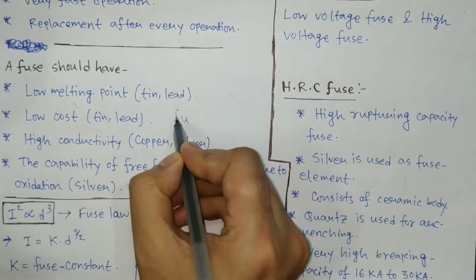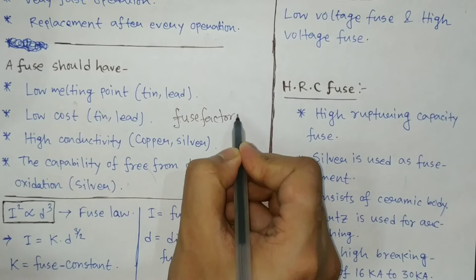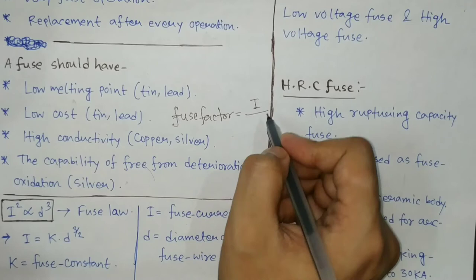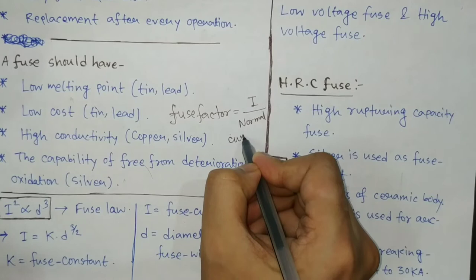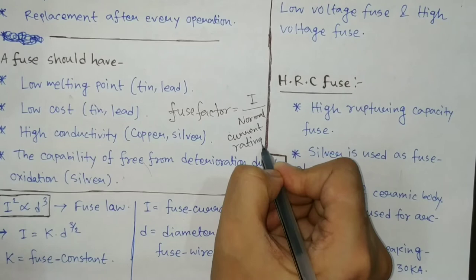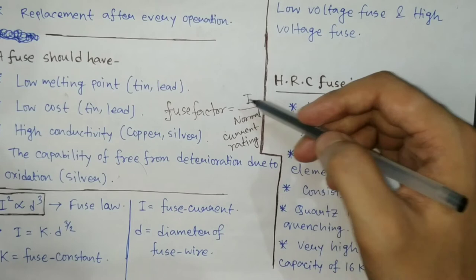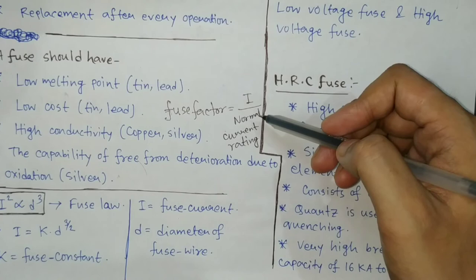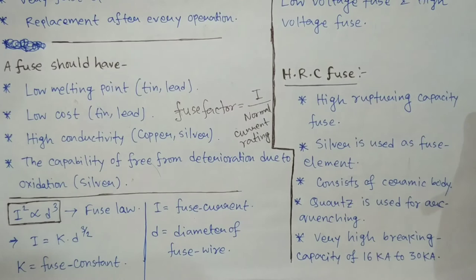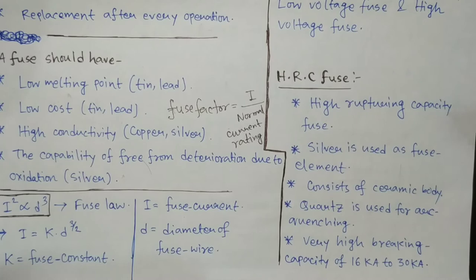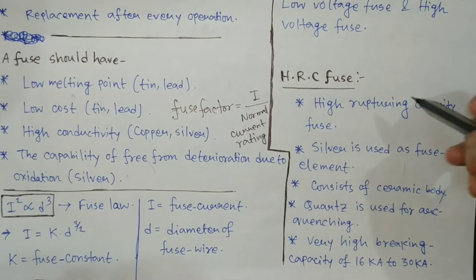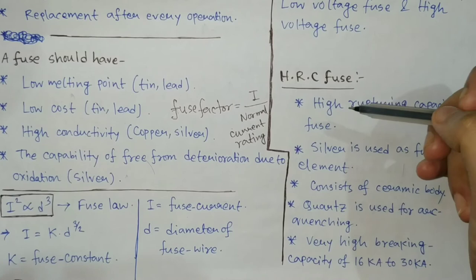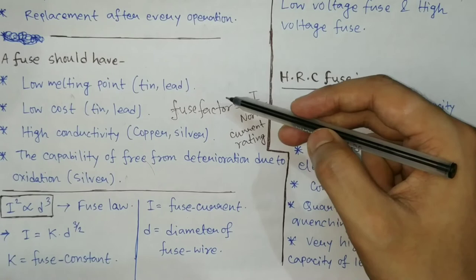There is a term called fuse factor. Fuse factor is I divided by the normal current rating of fuse. Fuse factor is always greater than 1. Normal current rating means the normal current value which the fuse can carry without getting overheated or melted during normal operation. It is always desirable that fuse factor should be as high as possible.